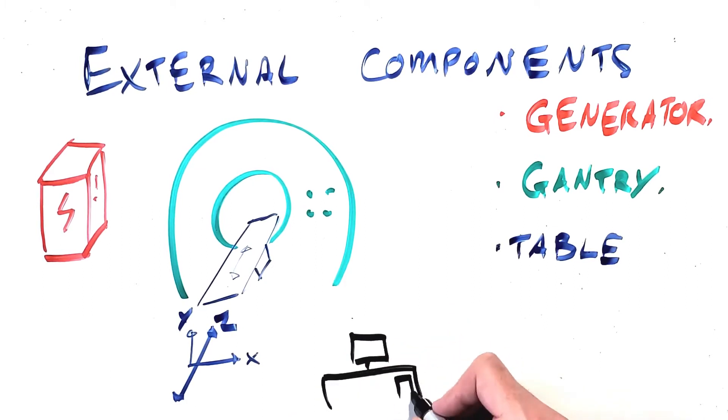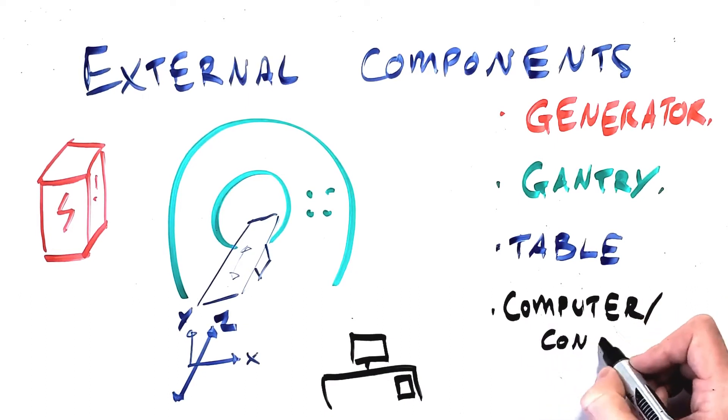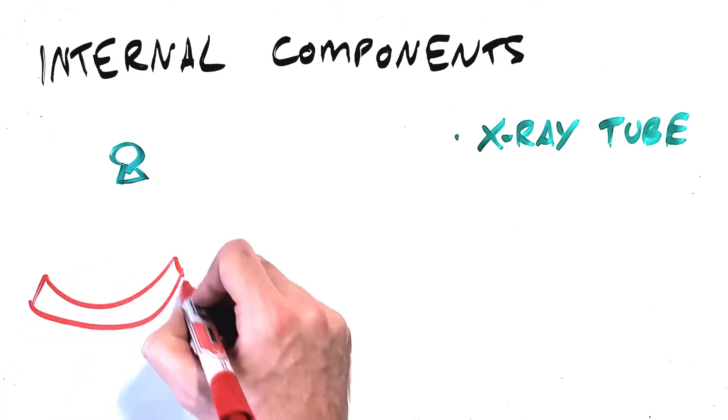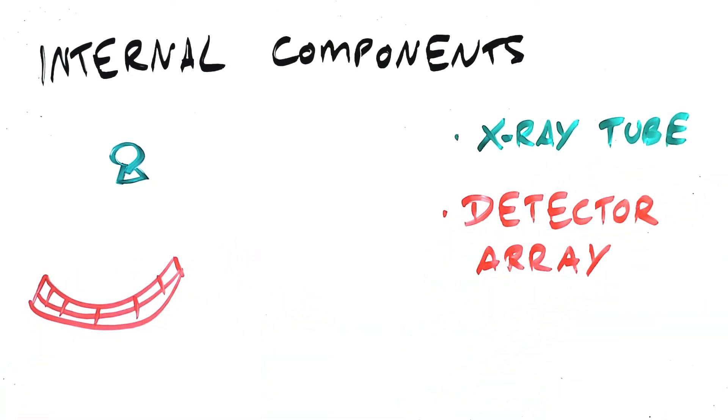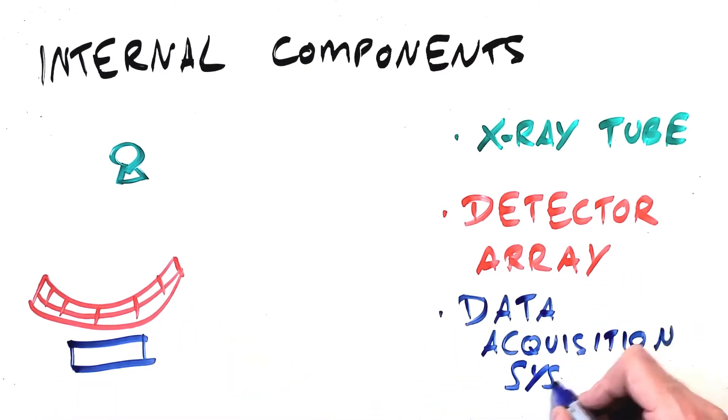And the computer and console from which the technologist acquires the scan which is in the control booth outside of the scan room. On the inside of the scanner is the x-ray tube which generates x-rays, the detector array which detects the x-rays transmitted through the patient, and the data acquisition system which receives data from the detectors and communicates that data to the scan computer.